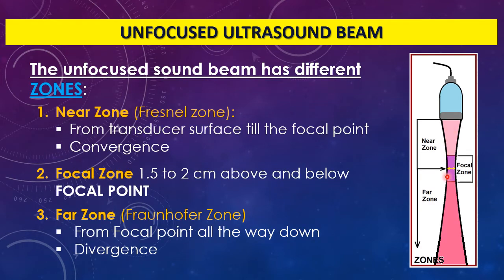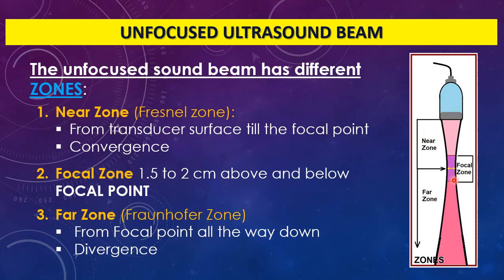Studying this ultrasound beam, we know it has a natural focal point and comes from a single element transducer. When we dissect its anatomy, we find three zones. The first zone runs from the transducer surface to the narrowest point of the beam — the focal point — and is called the near zone or Fresnel zone. Then we have the focal zone, which is the area around the focus, approximately one to two centimeters proximal and distal to the focal point. This is the narrowest zone in the beam.